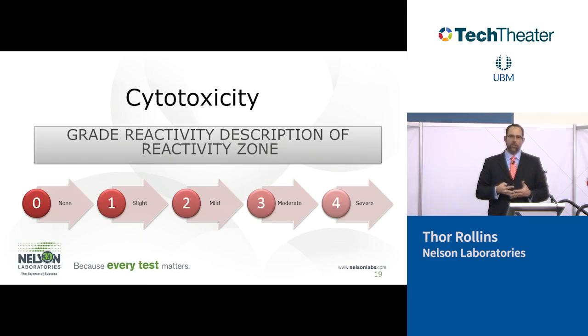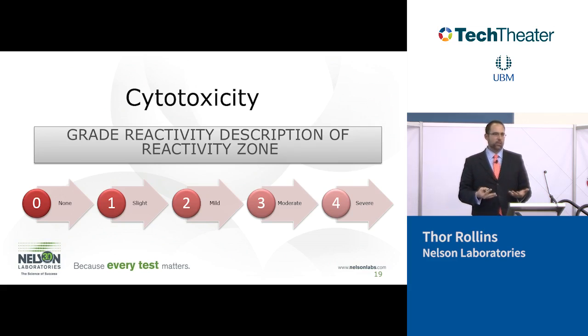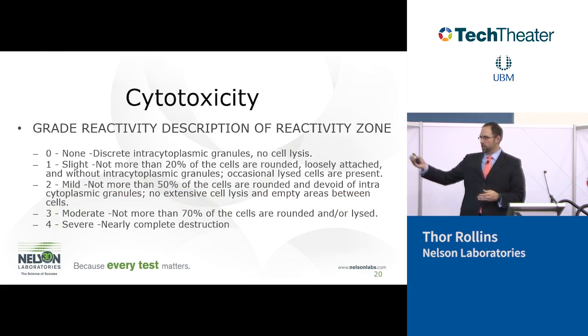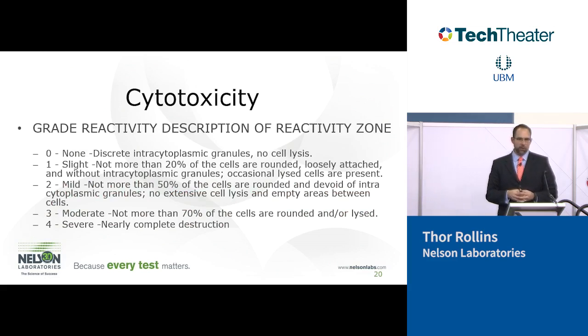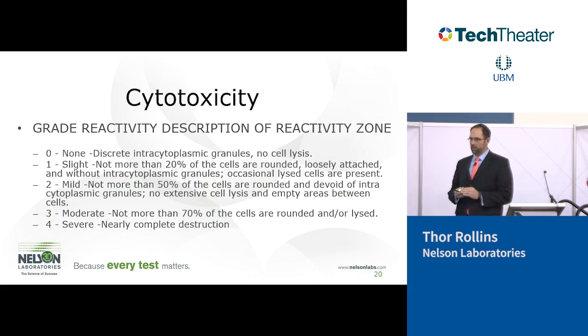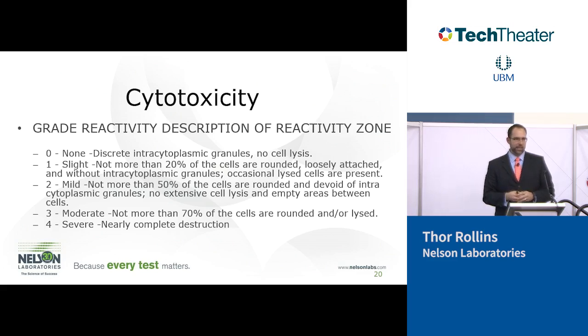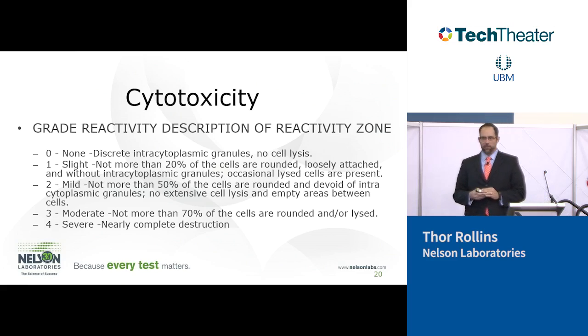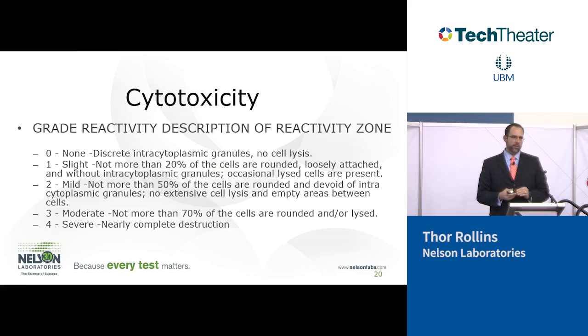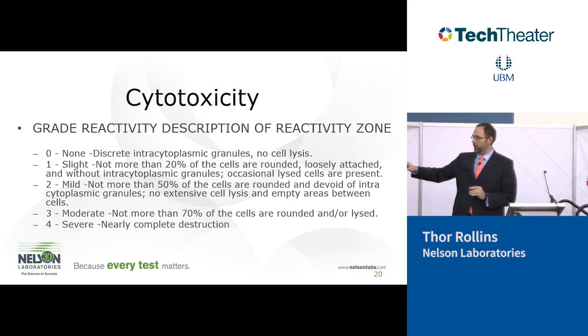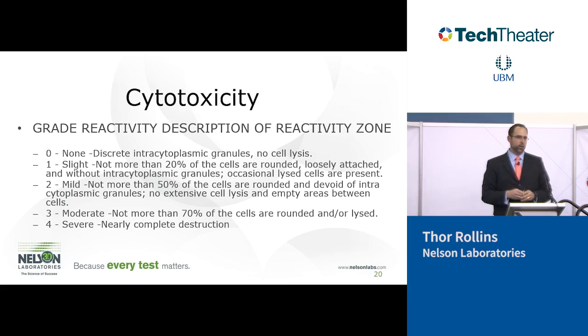Once we get the extract on the cells, then we do a score from 0 to 4. And this scoring criteria is in the standard. A 0 is no cytotoxicity whatsoever. A 1 is less than 20% of the cells have some cytotoxicity. A 2 is between 20 and 50%. A 3 is between 50 and 70%. And anything over 70% is a 4.